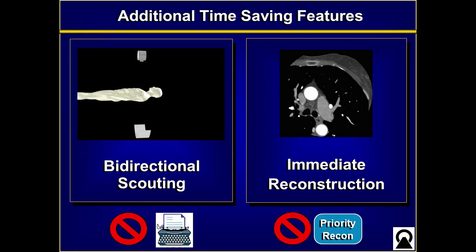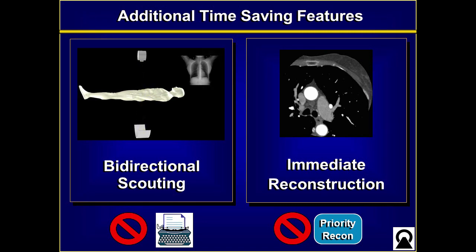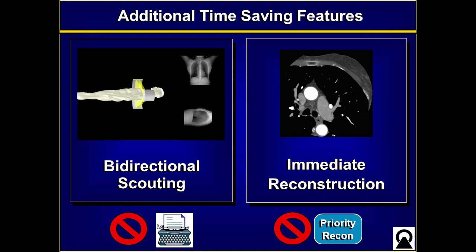Not all of the time savings is due to getting rid of the test bolus — there are other features that allow us to scan more quickly. Our old scanner operated like an old typewriter: you'd type a line, hit the carriage return, type another. Just like that, patients would go into the scanner and get scouted, come back out, then go in again. On our new scanner, as the patient goes in and gets scouted, the tube simply rotates 90 degrees and does the scout on the way out. It's like cup holders in a car — it might not be the reason to buy the car, but it sure makes a big difference.